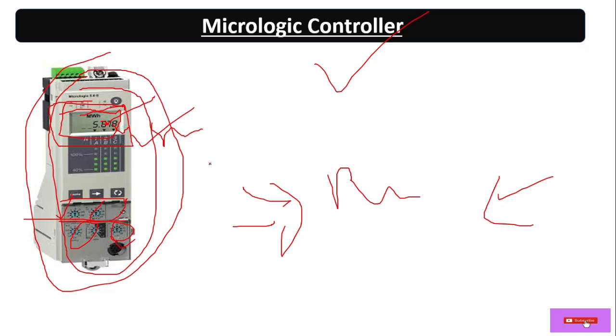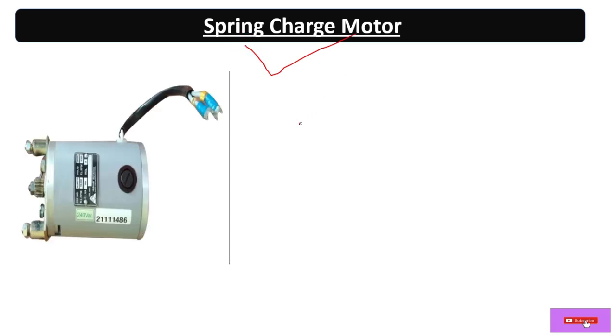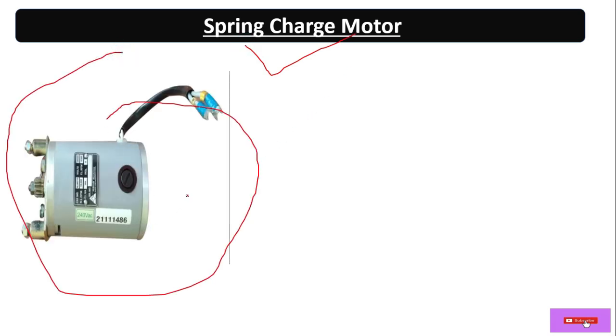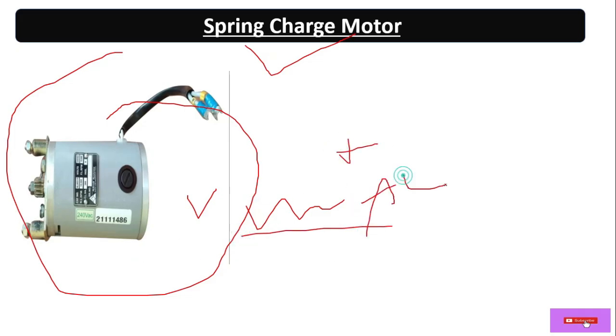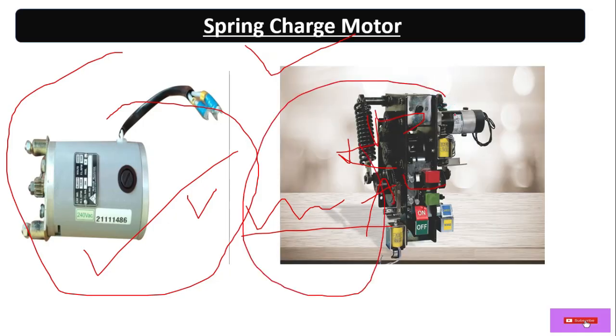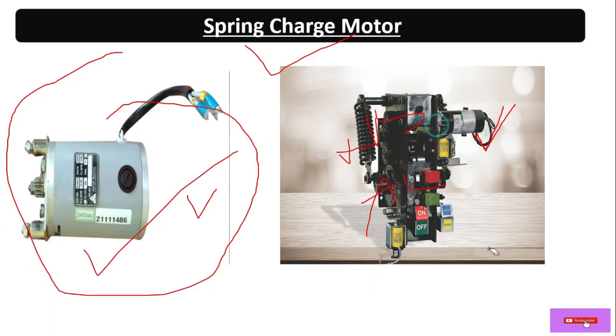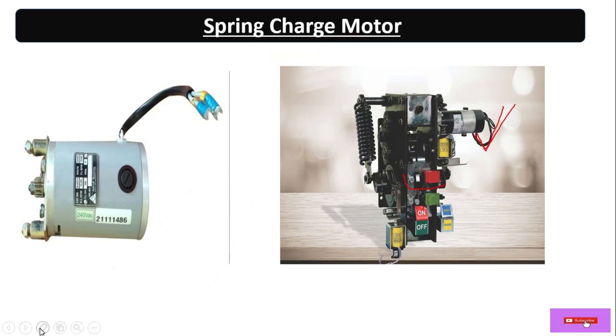On this display we can monitor the values during a visit to the LT panel or breaker. Another part is the spring charge motor — this is a universal motor that can operate on both AC and DC. This spring charge motor provides the necessary tension; the moving contact always requires the spring to be charged.